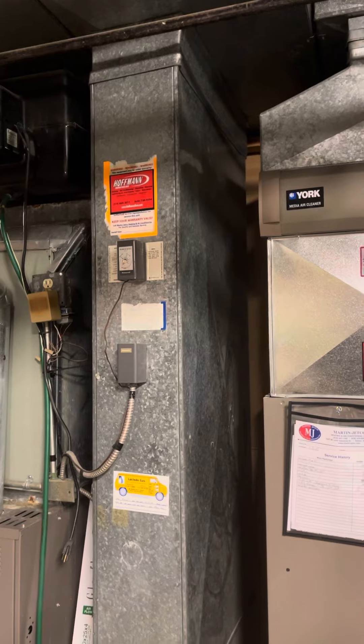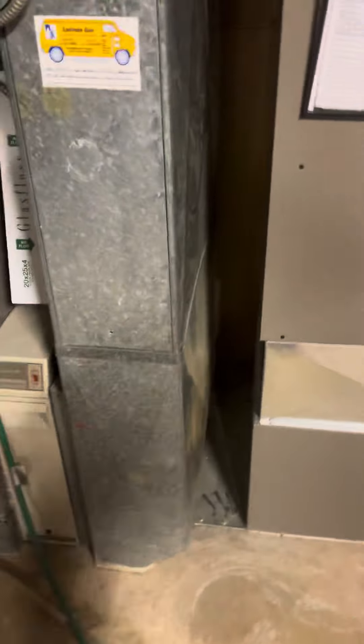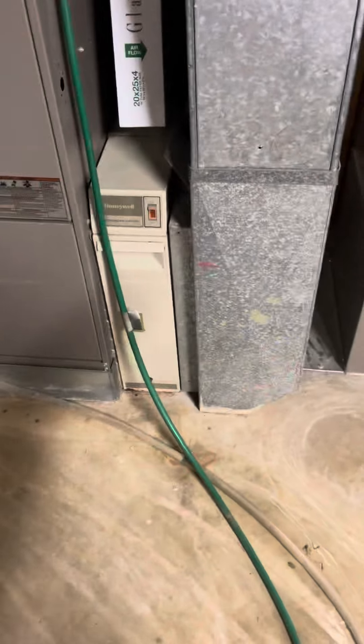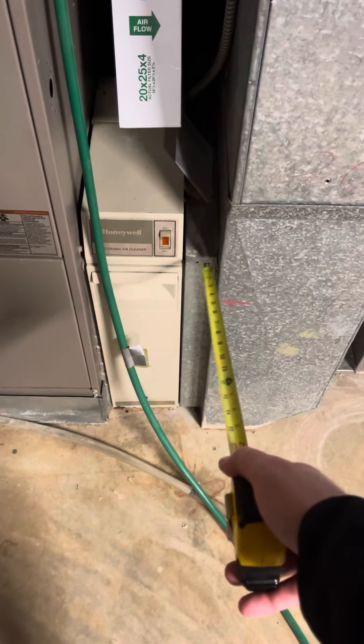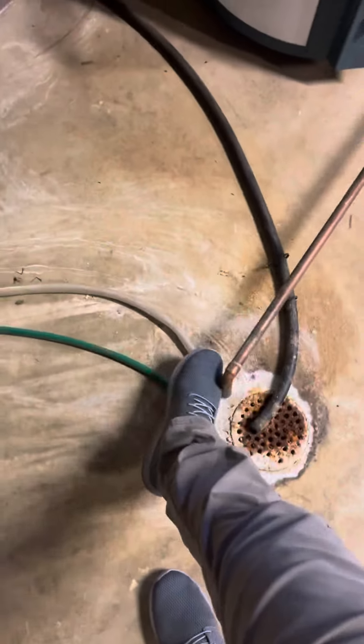I'll probably end up doing like a 20 by 25 on the return. We've got about six and a half inches of clearance — obviously we can't use all of that, but you've got about five inches you can play with there. Then we've got a six-inch filter housing and then a three-inch little spacer right there. The drains are right in front of the units here.